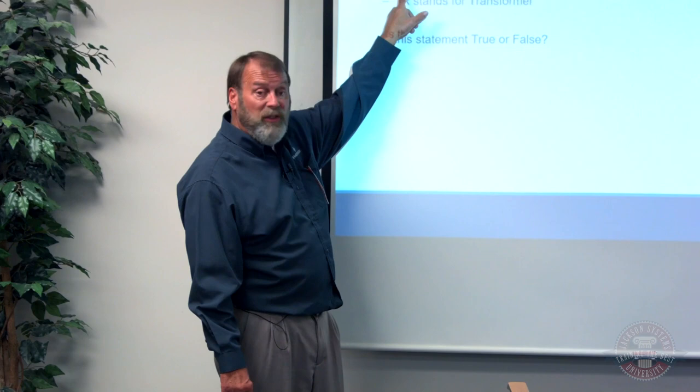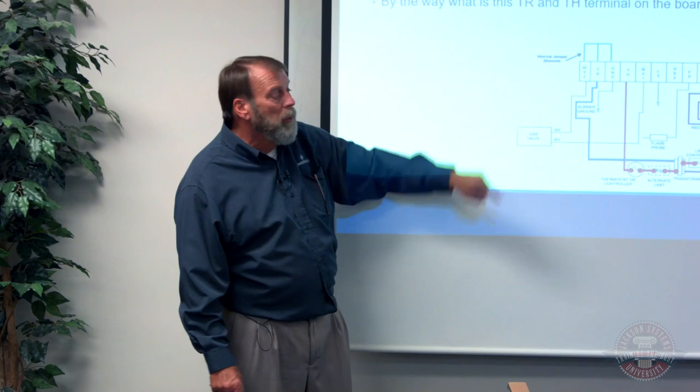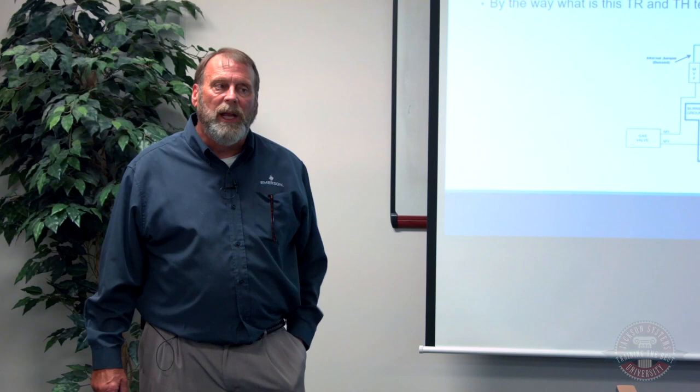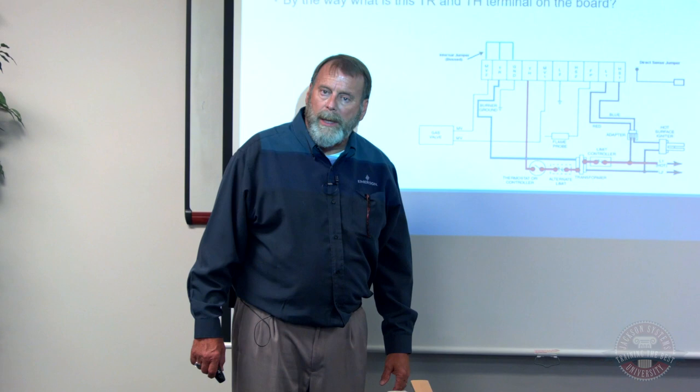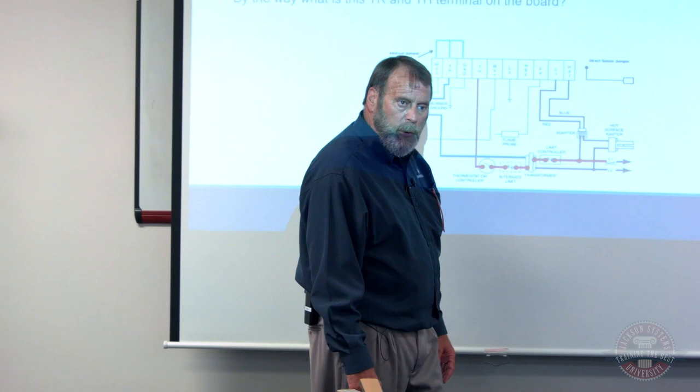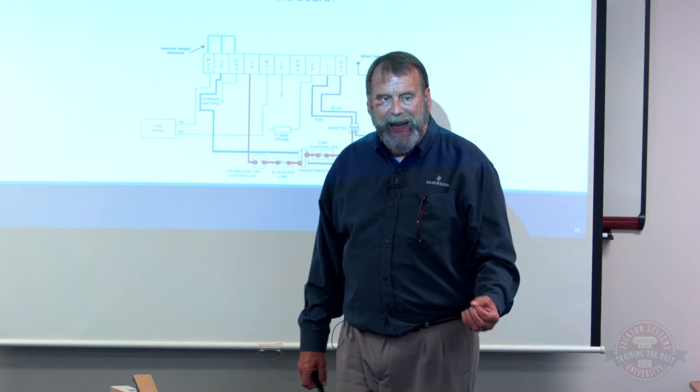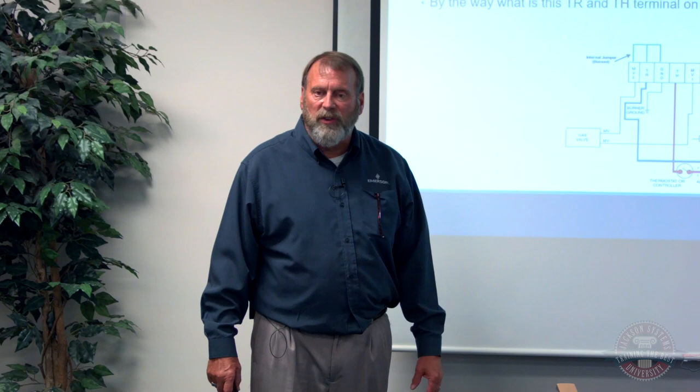And that's important when we go to the secondary. You need to know what the hot leg is of the transformer. And here's where it gets into a real issue. How do you identify the hot leg on a 24-volt transformer inside of a furnace? Has anybody here done it? Using your voltmeter, you would think, oh, I put that there and I go to ground. No. You literally have to take all the wires off the backside of the secondary and then check it to see if you can find either continuity or voltage coming through.